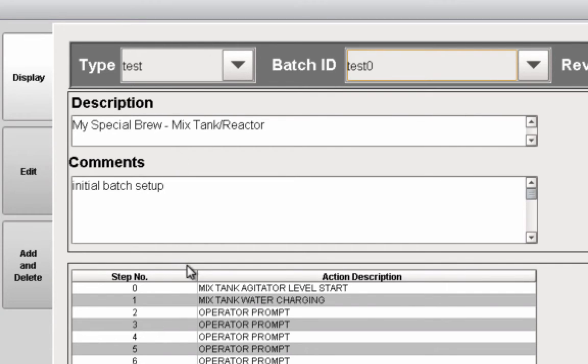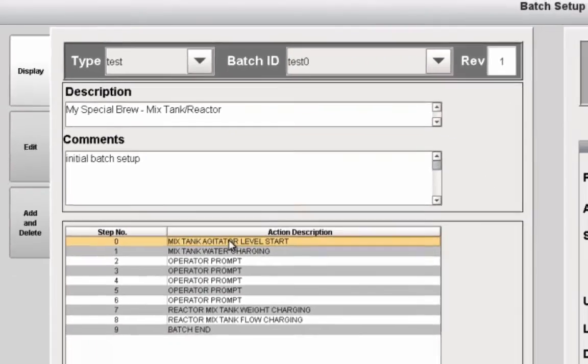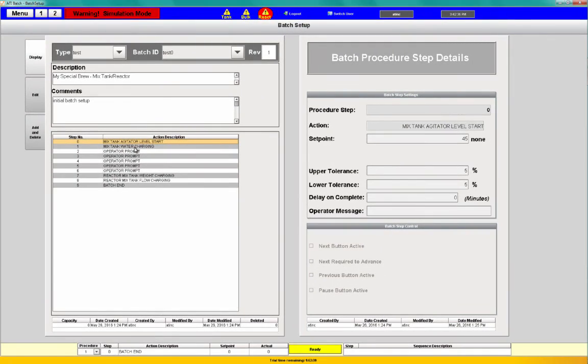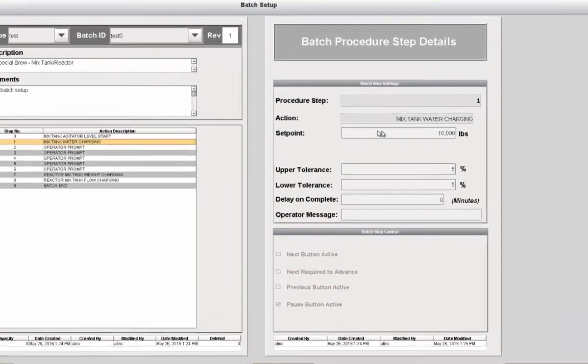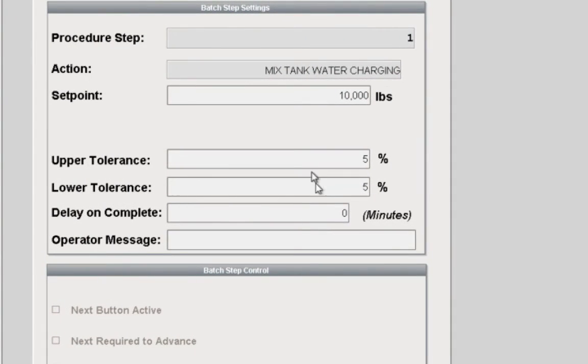Let's look at the one we just ran — test zero, My Special Brew. Now you can see what this procedure is made up of, what sequences are part of it. For example, there's the mix tank agitator — it's a level start, so we start the agitator once the level is high enough to avoid damaging it. For mix tank water charging, we're charging 10,000 pounds and we have tolerances. We can select things like next button active.